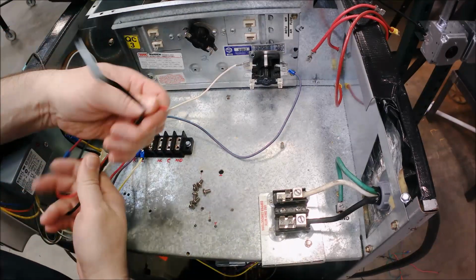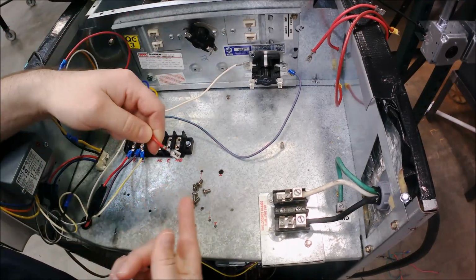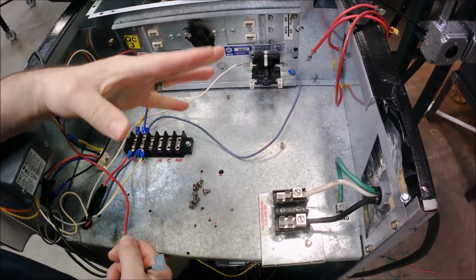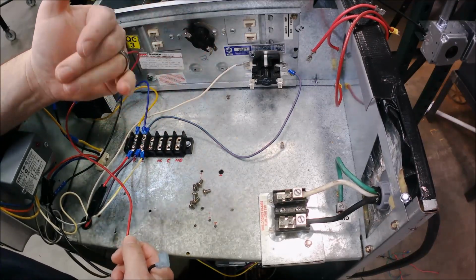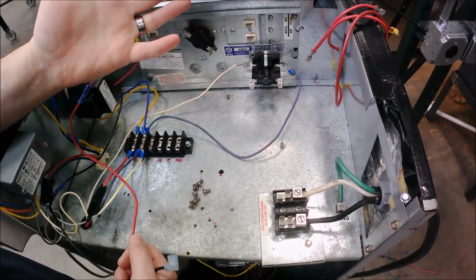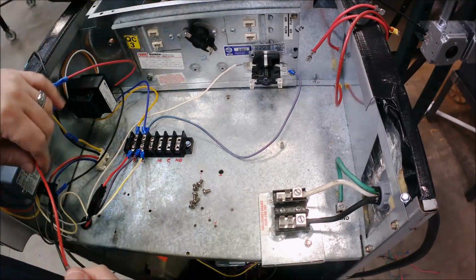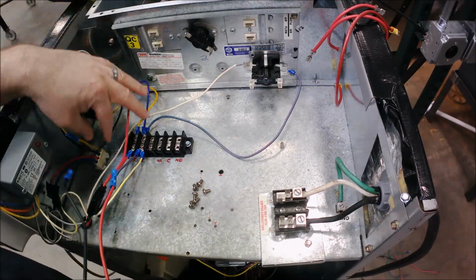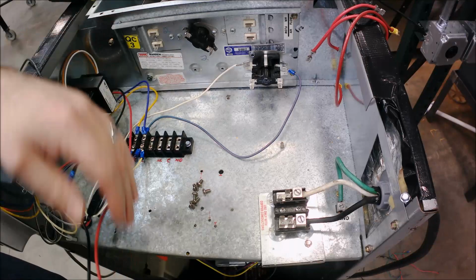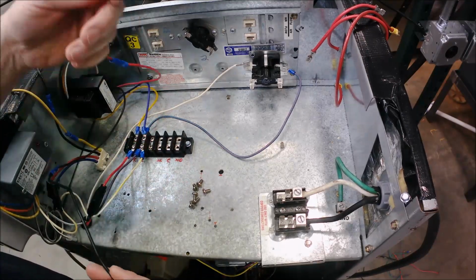So my transformer, right? Transformers and thermostats, they're two loads that are always on. They don't have a control switch to turn them on and off. They're on all the time as long as power's on. So what I'm going to do is, I know that my red and my black, I've already looked at the transformer. These are my high voltage connections here.